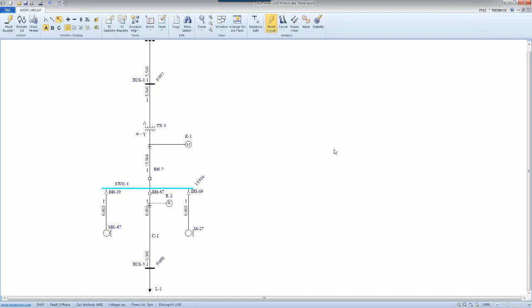So far, two highlights, two big points that we discussed. Number one, you can easily assume that the short circuit current or contribution on this bus remains the same and then pick this value with the longest trip time and use it to calculate the incident energy, which has a lot of deficiencies. Or you can go and in each iteration look at what branches have stopped contributing and then take them off. Just delete them, remove them from the rest of the calculation.